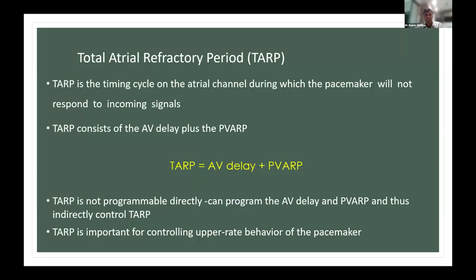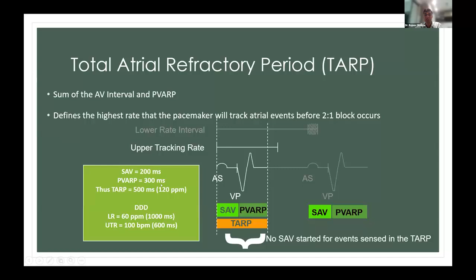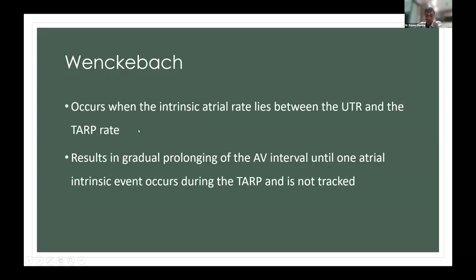Here TARP is 500 milliseconds. So the upper rate the pacemaker can go is 120 with this setting. Suppose we want 150, then we have to decrease one of these. This is commonly asked in exams also: what is pacemaker Wenckebach? When there is an intrinsic atrial rate which lies between the upper tracking rate and the TARP rate, then there will be pacemaker Wenckebach. I'll show it in the figure.